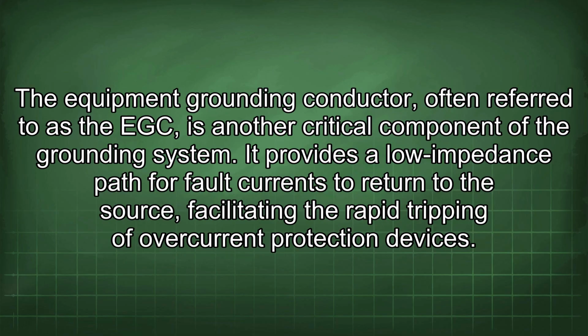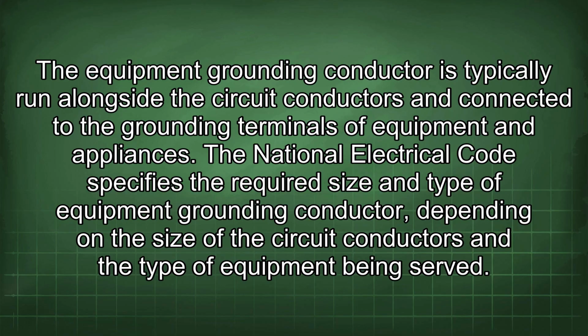The equipment grounding conductor, often referred to as the EGC, is another critical component of the grounding system. It provides a low impedance path for fault currents to return to the source, facilitating the rapid tripping of overcurrent protection devices. The equipment grounding conductor is typically run alongside the circuit conductors and connected to the grounding terminals of equipment and appliances. The National Electrical Code specifies the required size and type of equipment grounding conductor, depending on the size of the circuit conductors and the type of equipment being served.